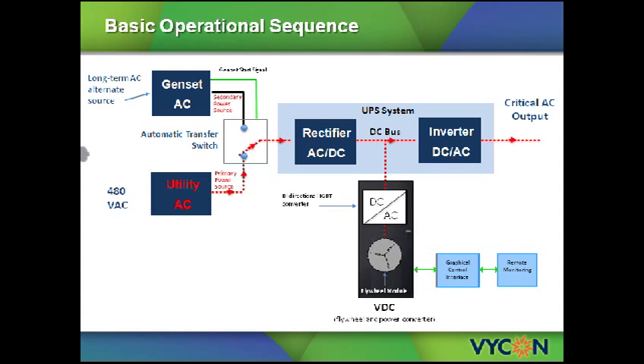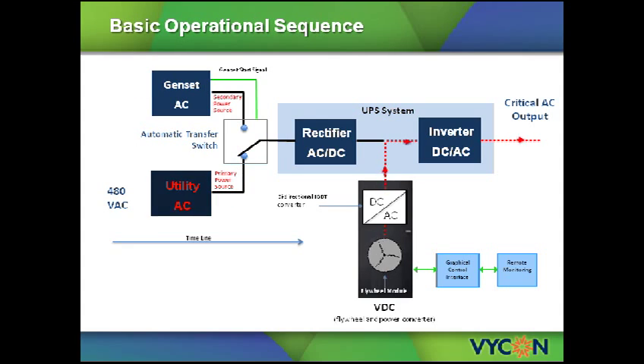Should the utility power fail due to maybe a lightning strike or other reason, the input power to the UPS will be lost, and the UPS rectifier output DC voltage will decline rapidly. The VDC, which is constantly monitoring the DC bus, will sense that an outage has occurred and will instantaneously start to convert the stored kinetic energy in the flywheel into DC electrical energy. This electrical energy is used by the UPS inverter to continue to supply uninterrupted, clean, and stable AC power to the critical load.